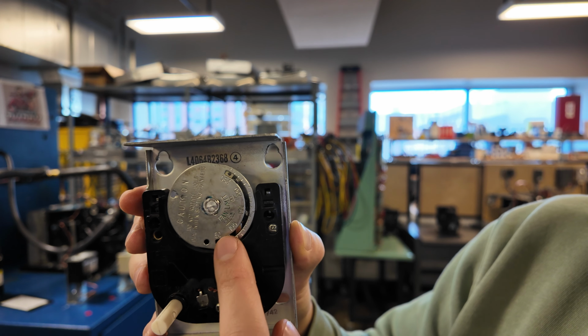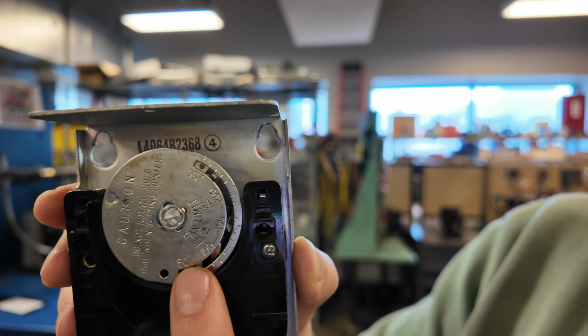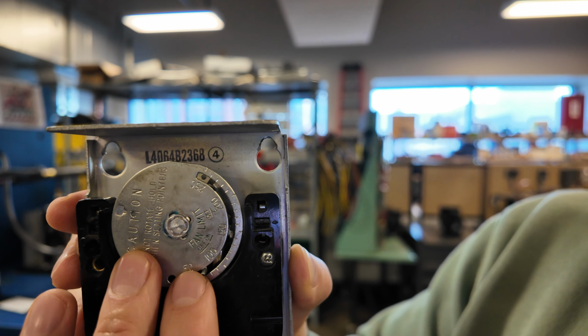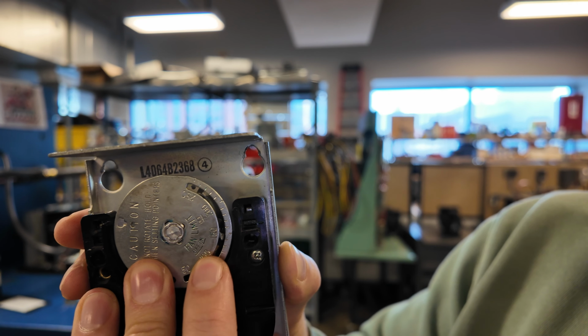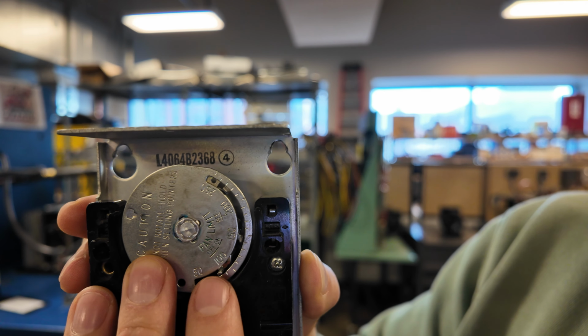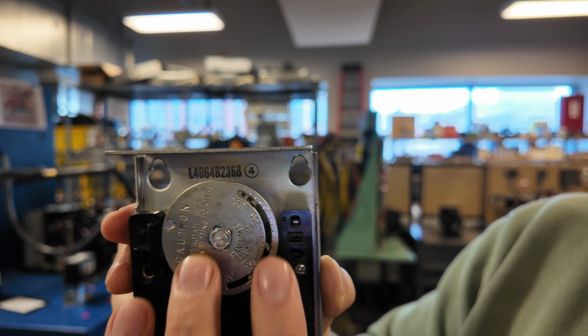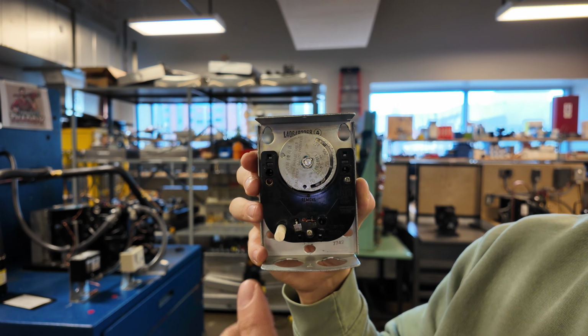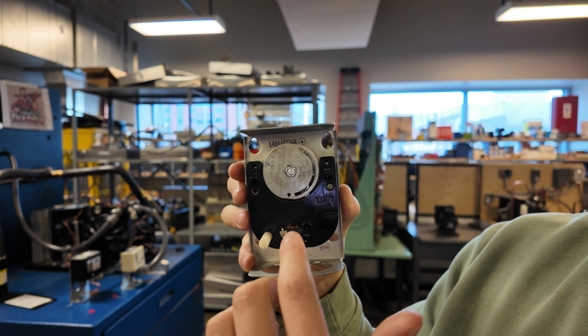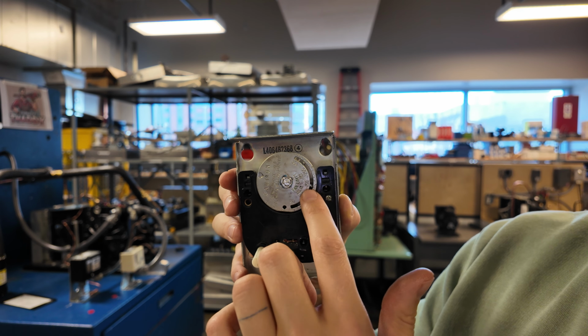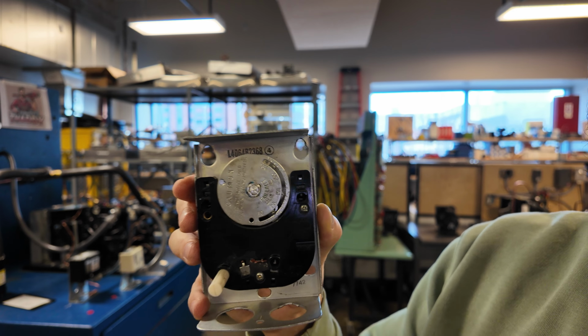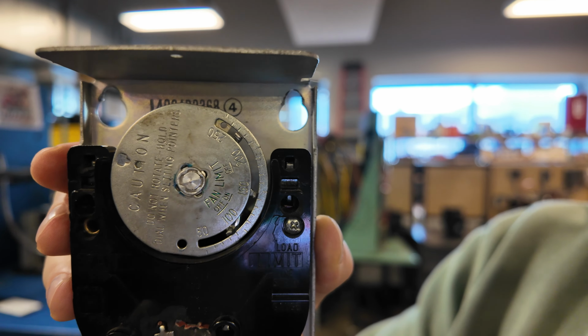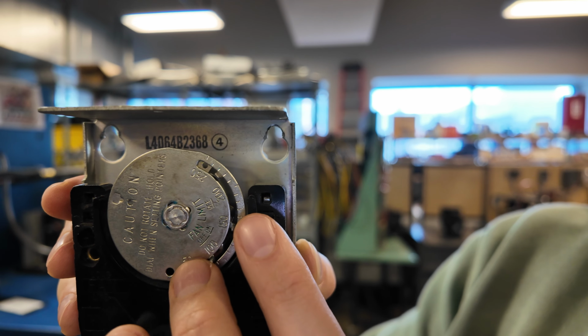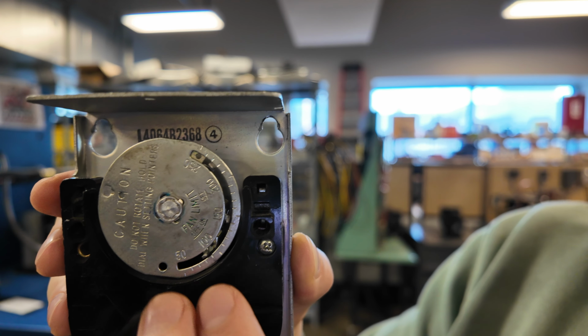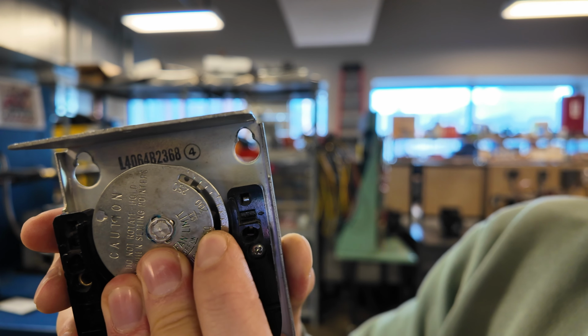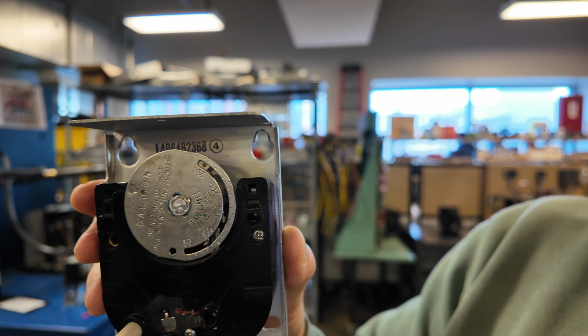They also call it auto and summer mode, depending on the manual. So the first arm here, if you were to adjust this, this would be your cutout set point. Usually I like to set my cutouts to around 90 degrees Fahrenheit. Then you're going to set your cut-in set point. This is when your heat turns on and your heat exchanger is building heat. There's going to be a temperature delay, and when it hits that temperature, it's going to engage your furnace fan. You need to make sure the gap between your cutout and cut-in isn't too small, or your fan will short cycle. So I usually set these around 130 or so, personally, and that's where I like it.